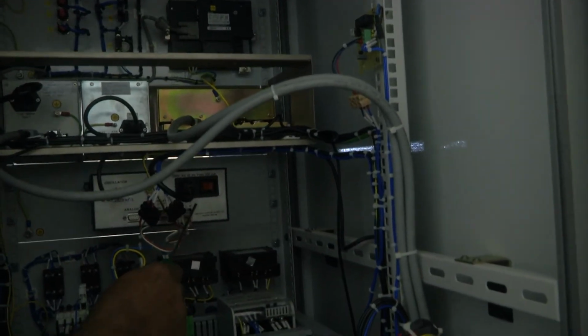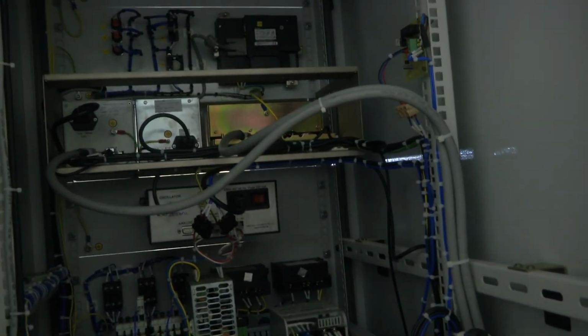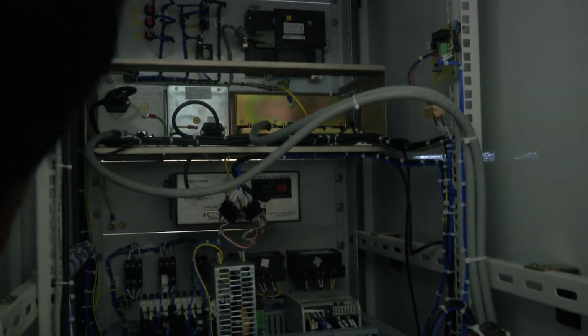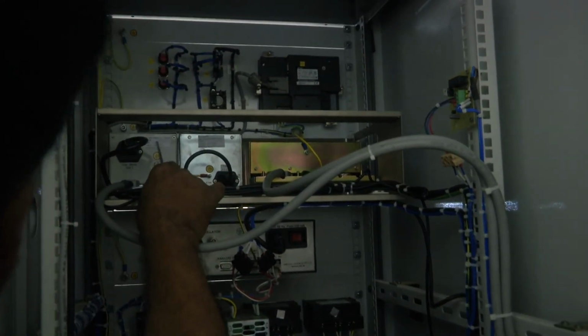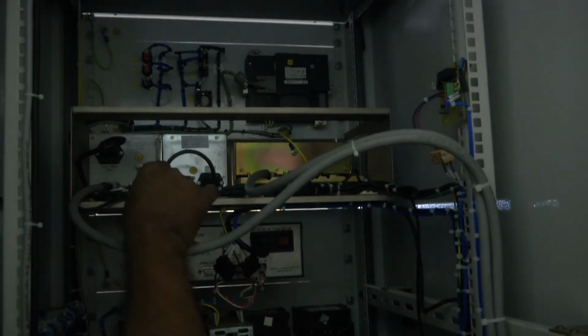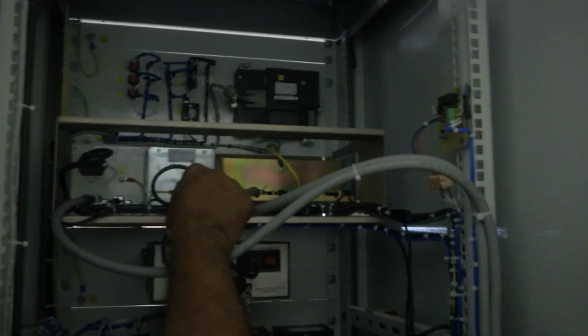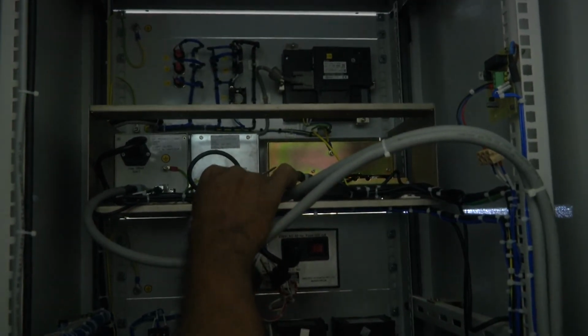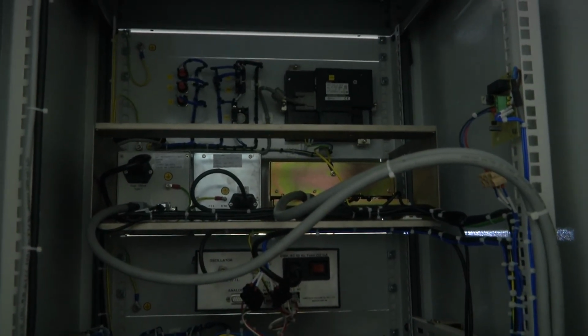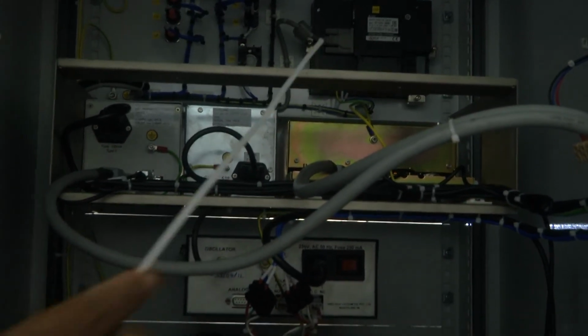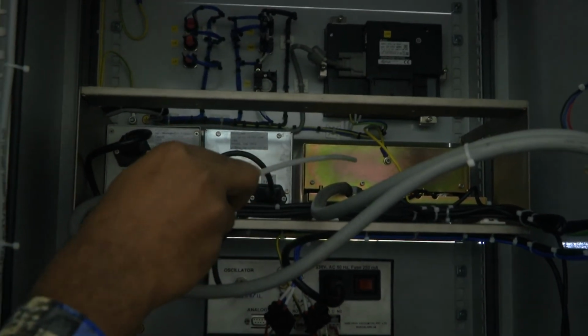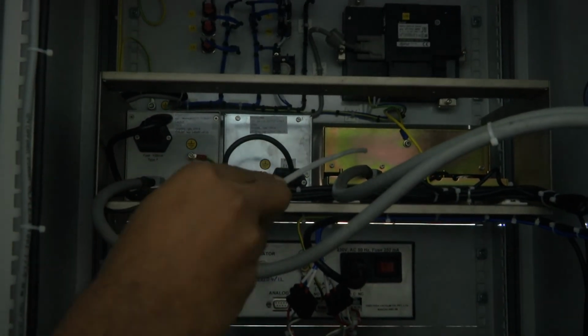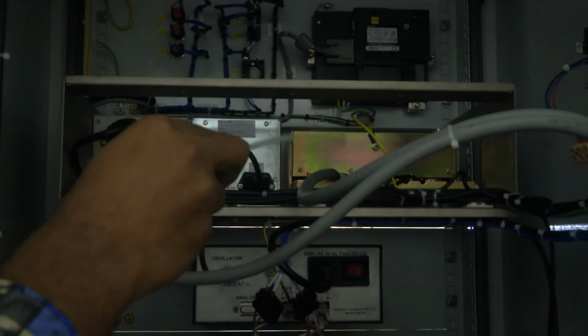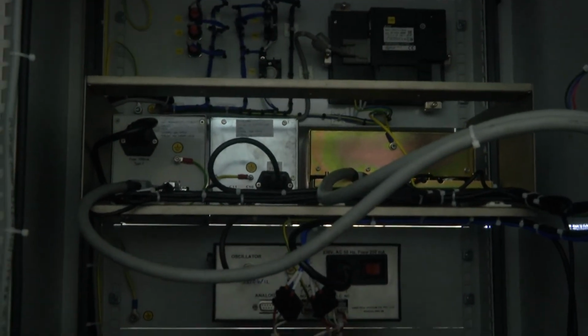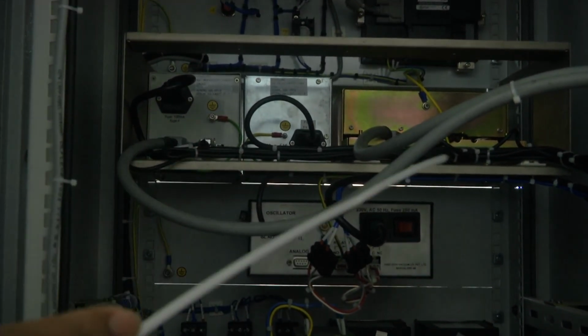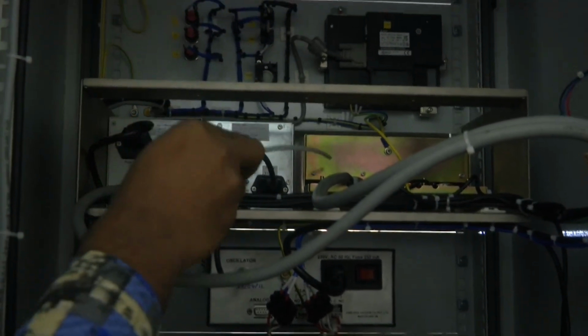This is the DTM, thickness monitor connection. From the QCM, I mean the crystal, it will come to this. See here, this is the EB motor turret indexer. This is the EB beam sweep controller. This is the high voltage unit, to select the EB gun power supply current and voltage. It is called one controller. By this controller we can set the EB gun current and voltage, and we can monitor from this. Through that connector it will go to the power supply unit directly. Yes, already interconnected with these cables. So those cables we will connect to this now. Yes, we have to monitor from this controller.